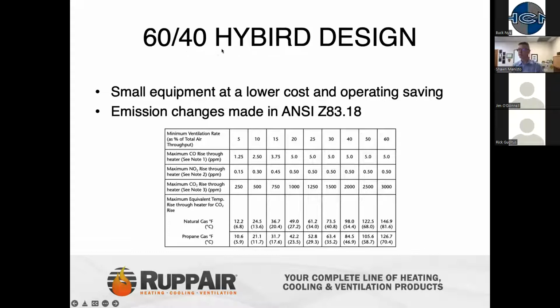So again, the 60/40 hybrid came from two things. Make sure we have a small piece of equipment at the lowest cost possible, but meet the best operating savings. So taking some of that 80/20 traditional concept and putting it into a smaller footprint, but then also making sure that we have the amount of fresh air needed to meet the emission levels for the ANSI standard and provide just a clean, safe heating product for the industry.